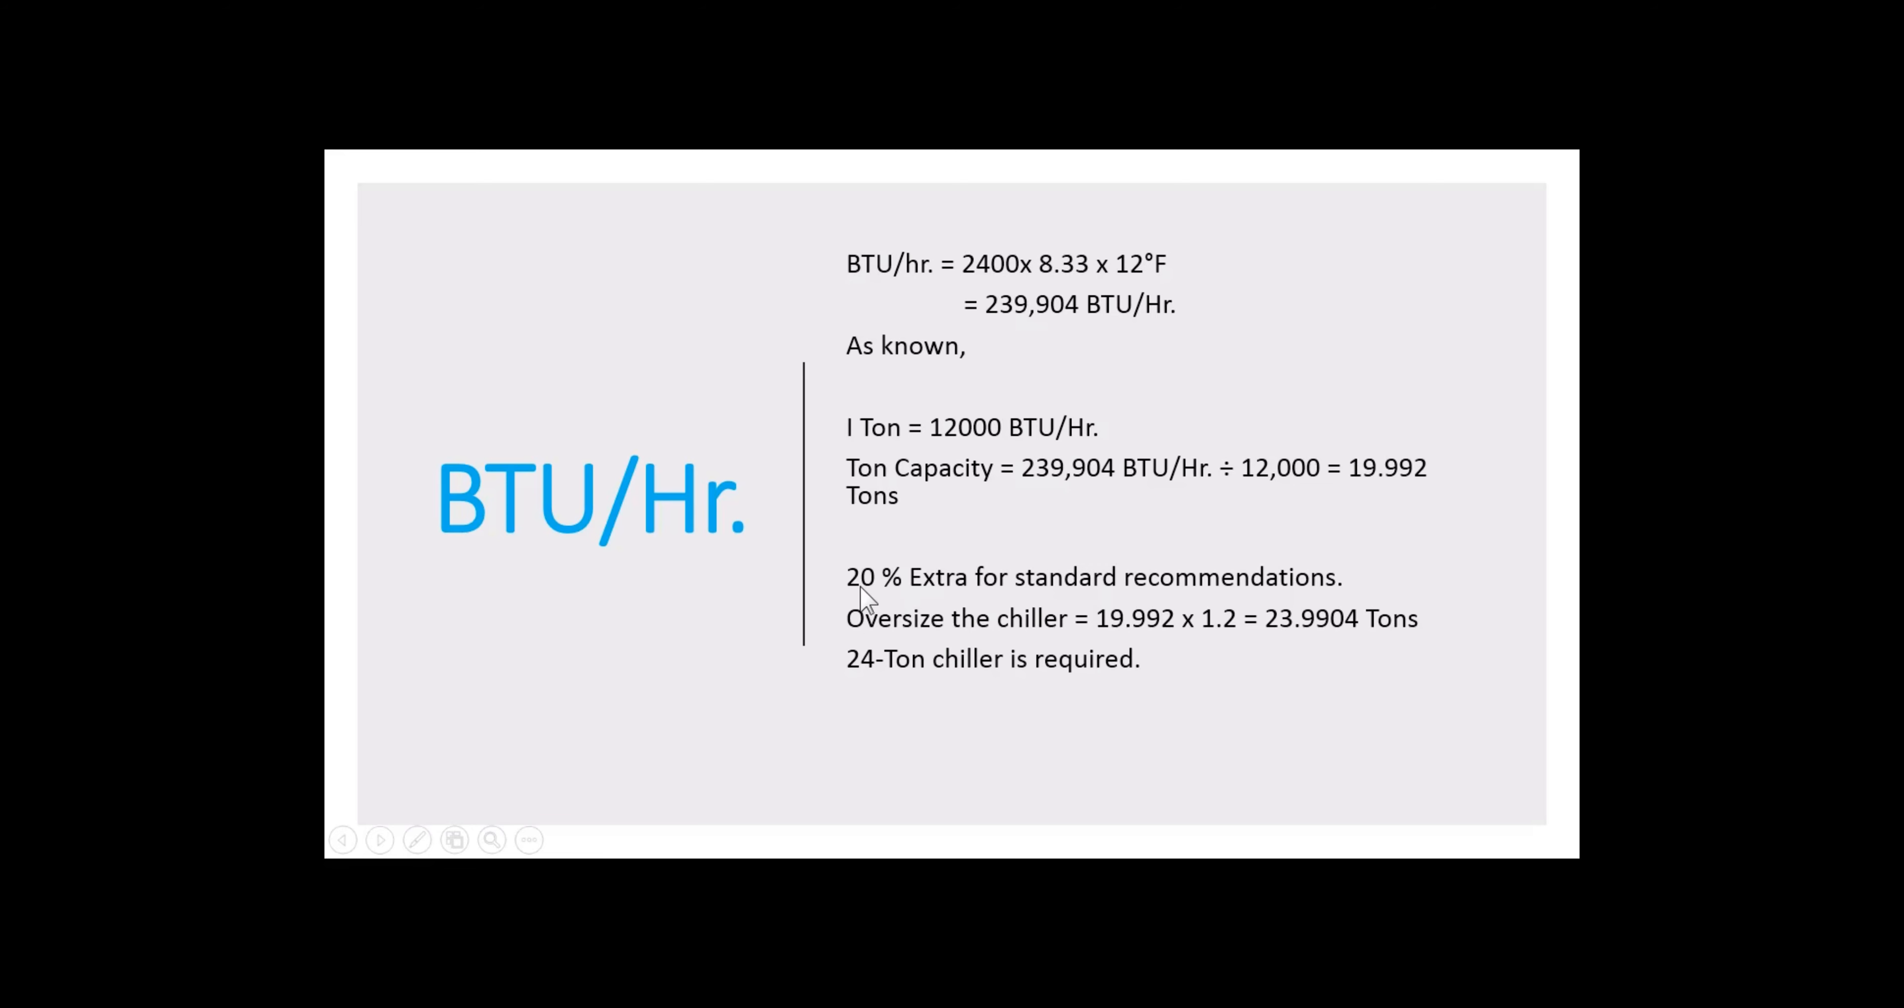Normally when we are designing the cooling towers, we need to always consider 20 percent more. This is a standard recommendation. If we increase the ton capacity by 20 percent more, then you can get 23.9 tons, which when we take as a round number, means 24 ton chiller is required.